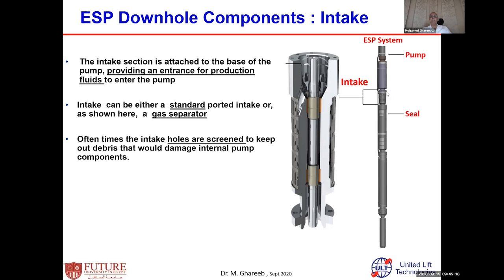This intake can be either a standard intake, if there is no gas in the well, or if I produce a water well and so on, or it can be a gas separator. Since it will take in the fluid and allow it to go to the pump, it can be like a gas separator. The gas separator separates a high volume of gas before entering the pump in order to improve the pump volumetric efficiency. If I use a standard intake, with no separator, usually this intake should be screened, putting some screens or filters on it to reduce the amount of debris and sand that can enter the pump.